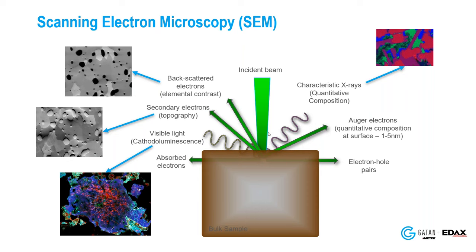The X-rays produce an EDS signal — energy dispersive spectroscopy — and that gives you quantitative chemical composition of the material. The backscatter electrons give you information about elemental contrast. The secondary detector, which is often the primary detector in an SEM, gives you information on topography. You can put a cathodoluminescence detector in and get visible light, and there are other detectors you can put in the microscope as well.